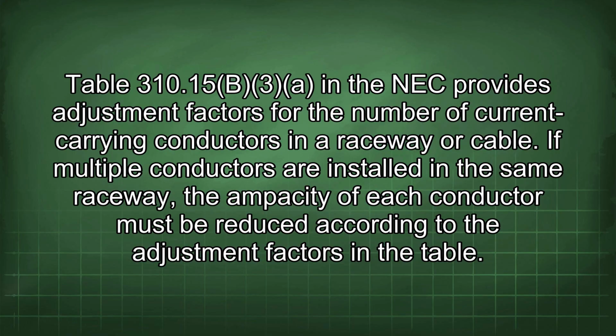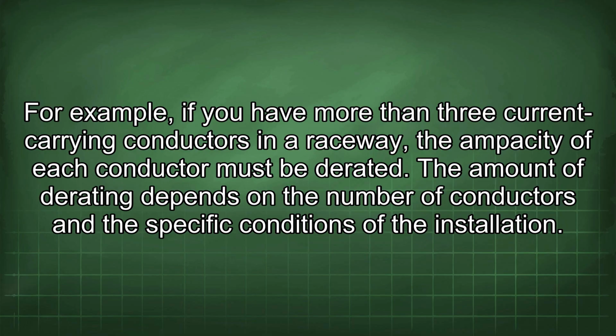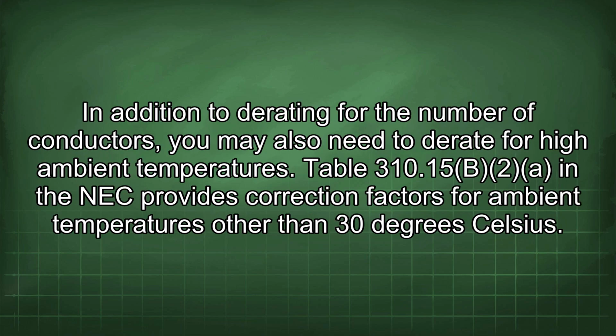If multiple conductors are installed in the same raceway, the ampacity of each conductor must be reduced according to the adjustment factors in the table. For example, if you have more than 3 current-carrying conductors in a raceway, the ampacity of each conductor must be derated. The amount of derating depends on the number of conductors and the specific conditions of the installation.